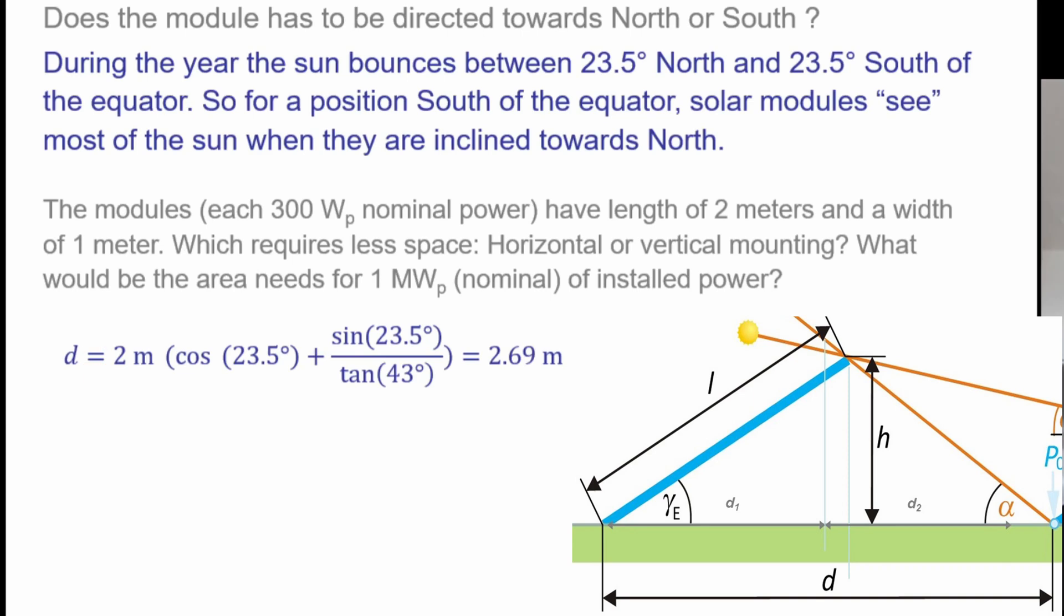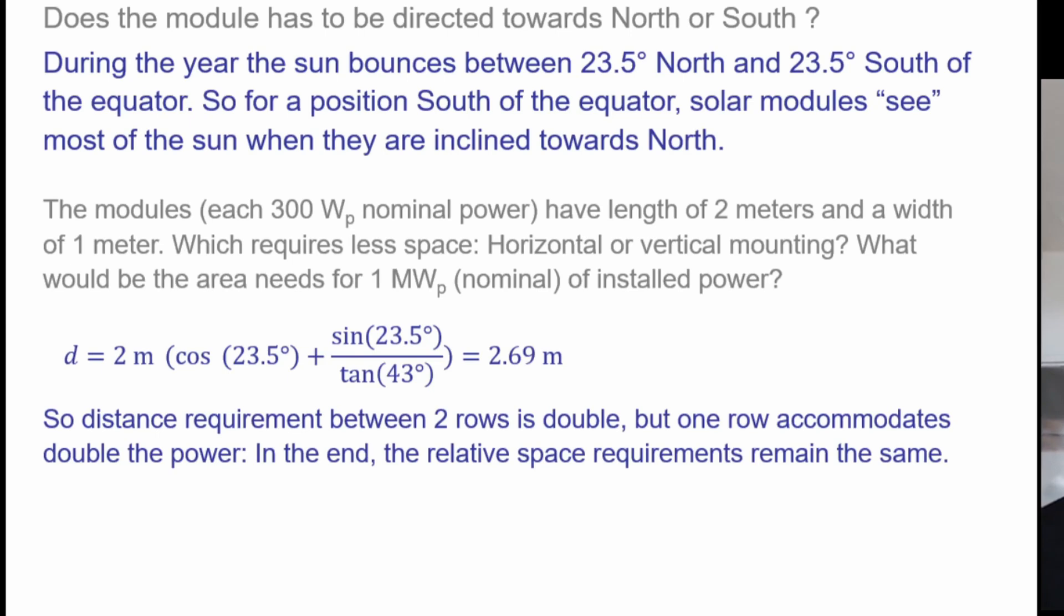And altogether we have a distance we have to keep at 2.69 meters. So the distance requirement between two rows is now double, but it accommodates the double amount of modules or double the power. At the end, this relative space requirement remains the same.